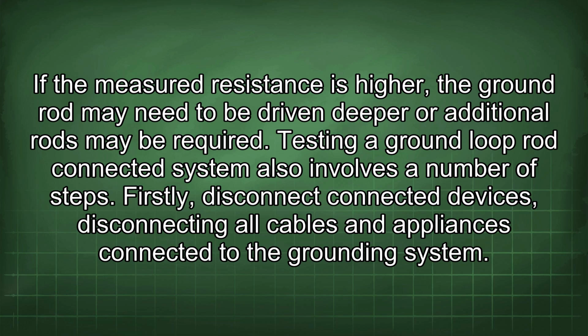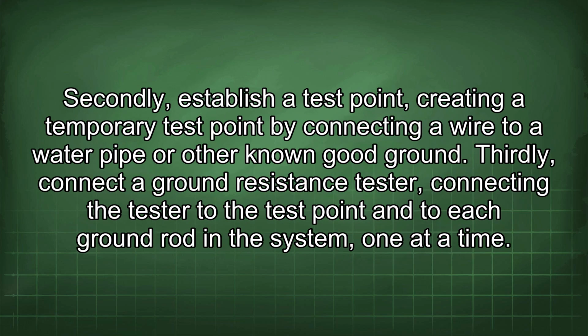required. Testing a ground loop rod connected system also involves a number of steps. Firstly, disconnect connected devices, disconnecting all cables and appliances connected to the grounding system. Secondly, establish a test point, creating a temporary test point by connecting a wire to a water pipe or other known good ground. Thirdly, connect a ground resistance tester, connecting the tester to the test point and to each ground rod in the system one at a time.